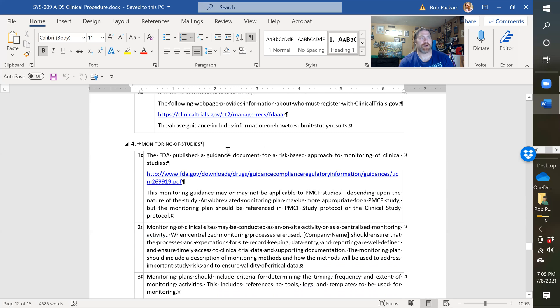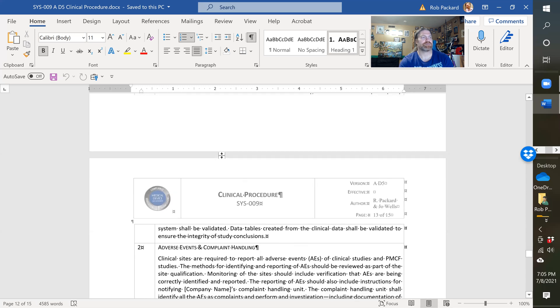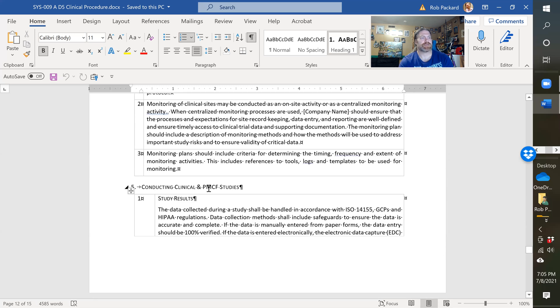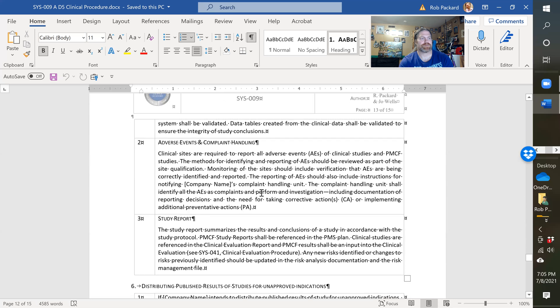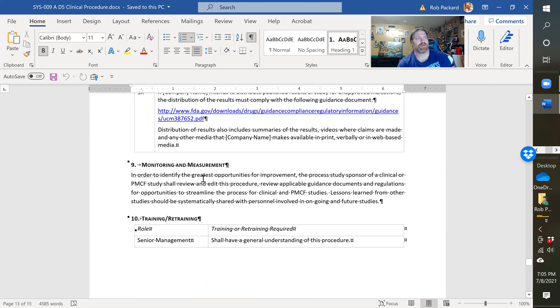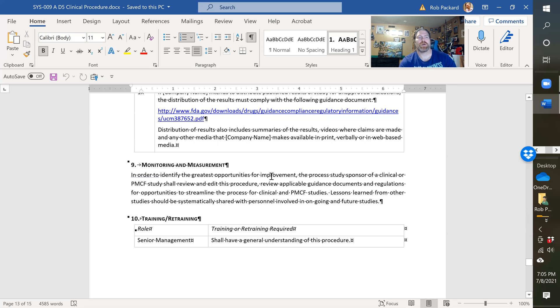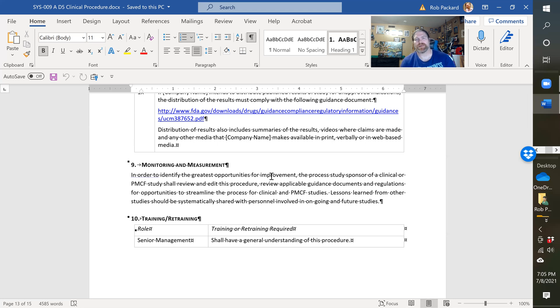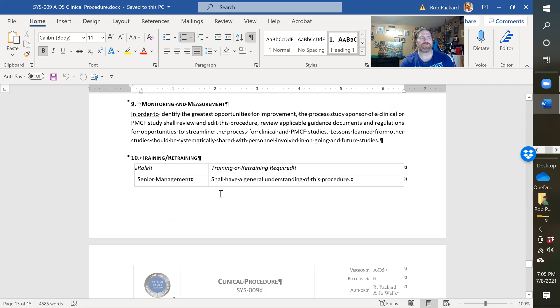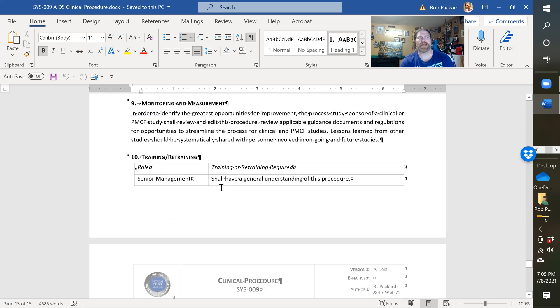We cover monitoring of studies, conducting clinical studies and PMCF studies, distributing published results for unapproved indications, and then monitoring and measurement. That's monitoring and measurement of this procedure - are you following this procedure? How many studies have you got going? Are they being done on time? Are there any deviations? This is how you would measure your clinical process - are you reporting things on the timeline you're supposed to be?